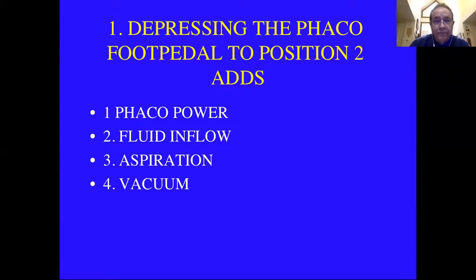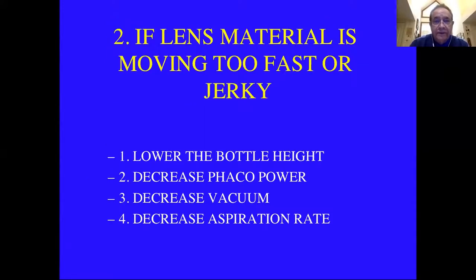Question two: If lens material is moving too fast or jerky, what do you need to do to correct that? Do you lower the bottle height, decrease the phaco power, decrease the vacuum, or decrease the aspiration rate?